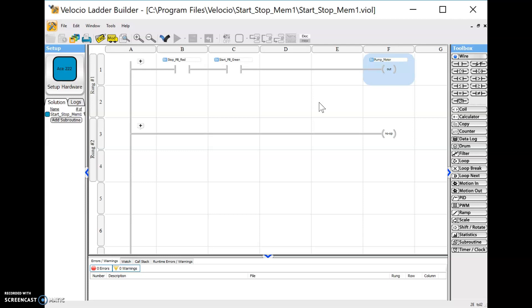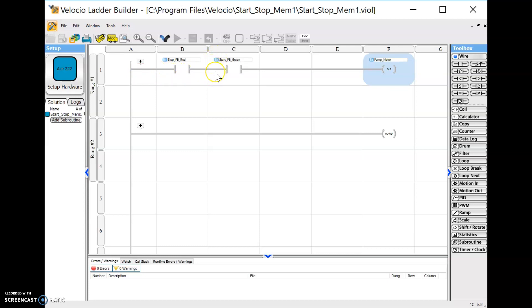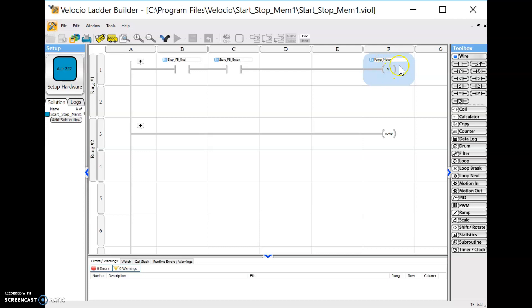So this thing would work just like this because for the stop button in the real world, the physical button we're going to wire to this has contacts that are normally closed. You push the button, they open up. So it's going to allow logical continuity through this contact. And it's going to be waiting right here until you press the start button. Once you press the start button, it's going to allow logical continuity to pass through the input conditions. And they will induce this output to register a one. It'll energize this output. The pump motor will then come on, if that's what you have the physical terminal hooked to. It would behoove of you to do so if you want your system to run.